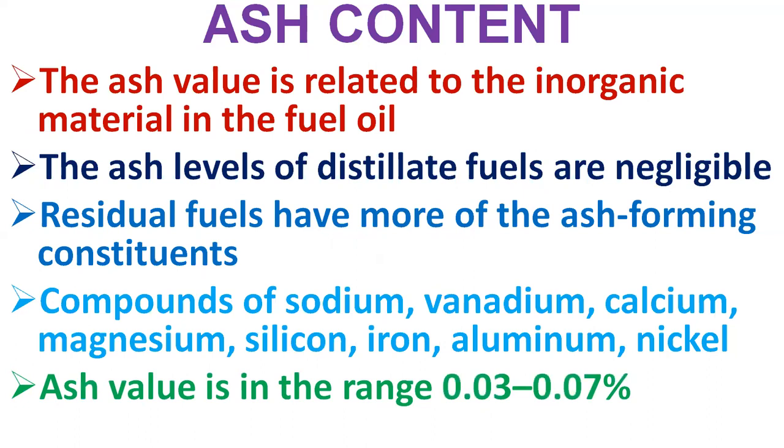Excessive ash in liquid fuels can cause fouling deposits in the combustion equipment. Ash has an erosive effect on the burner tips, causes damage to the refractories at high temperatures, and gives rise to high temperature corrosion and fouling of equipment.